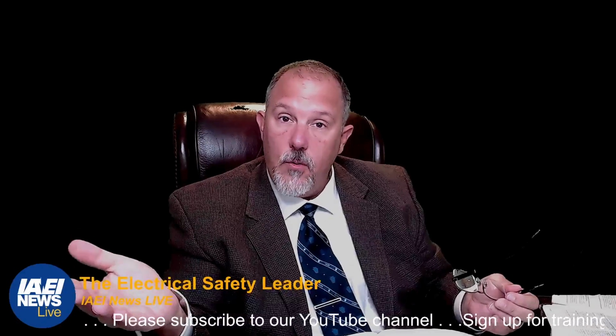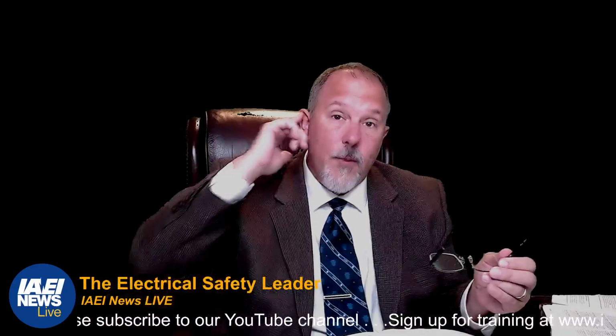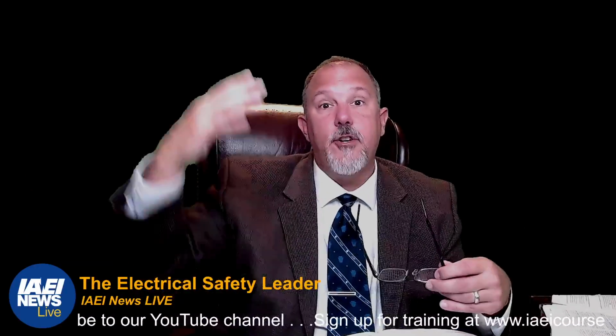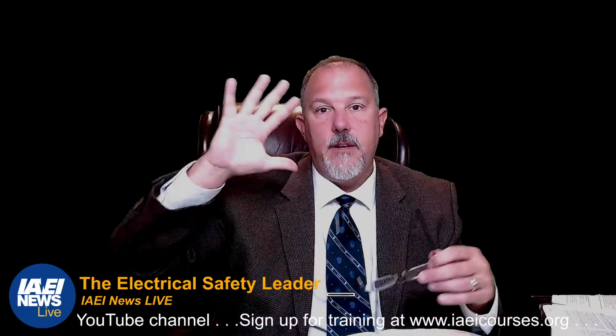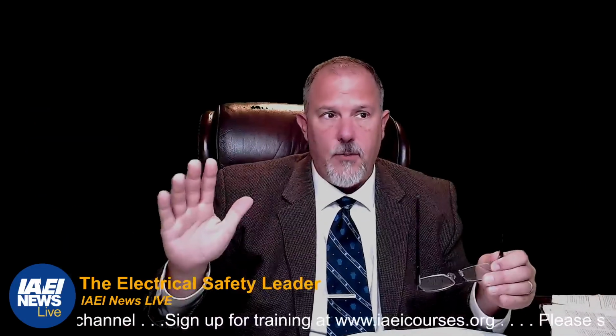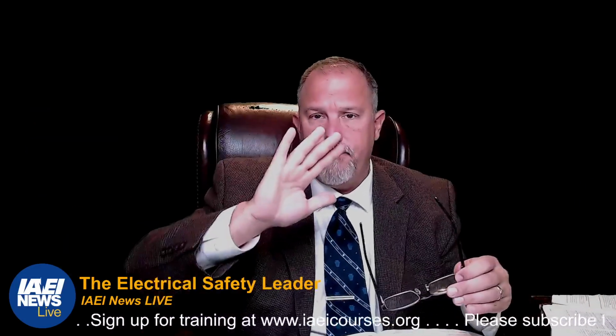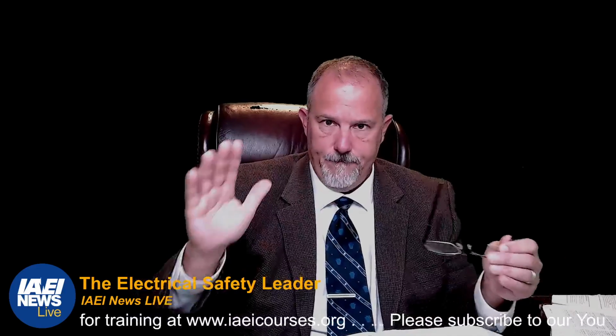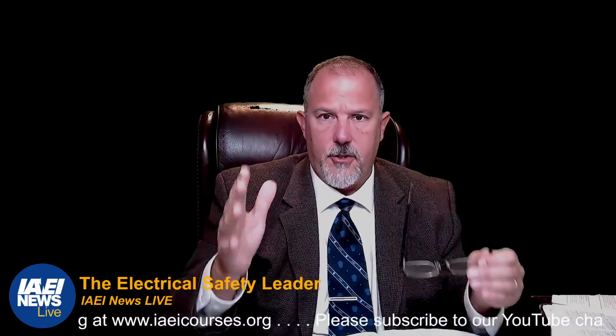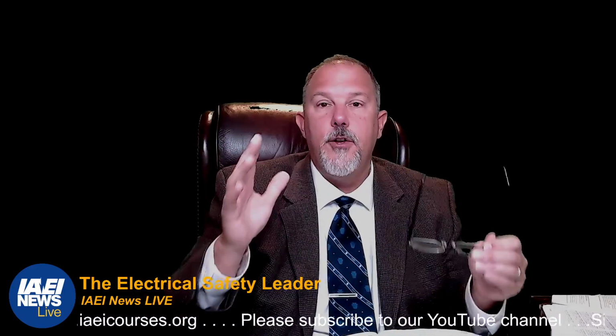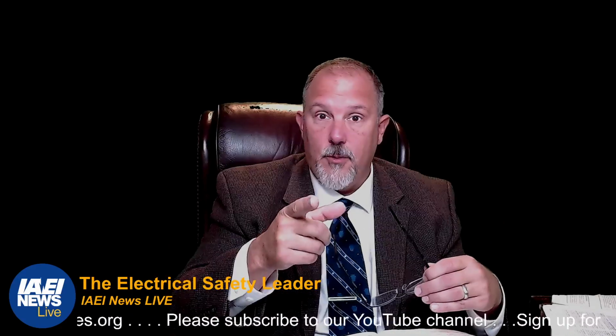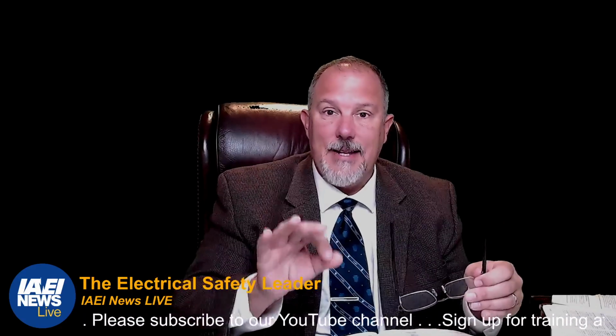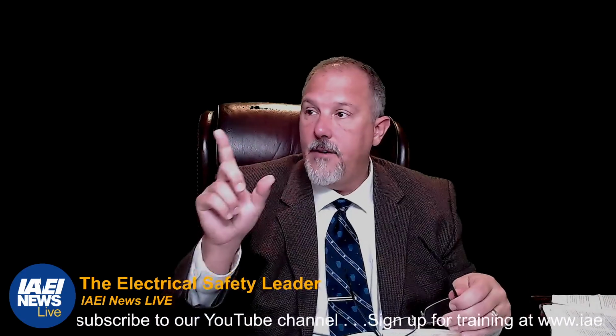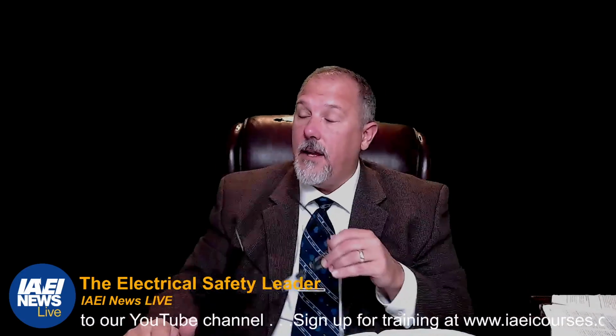say you have a school and you have a bunch of panel boards that you want to update. You could take the interiors out, not bother the infrastructure. You don't need to worry about plaster and all that good stuff. You're using the existing enclosure. All the wires are intact. You're going to take the interior out, the panel board, put a new panel board inside that enclosure, and 408.9 is going to govern what you can and can't do.